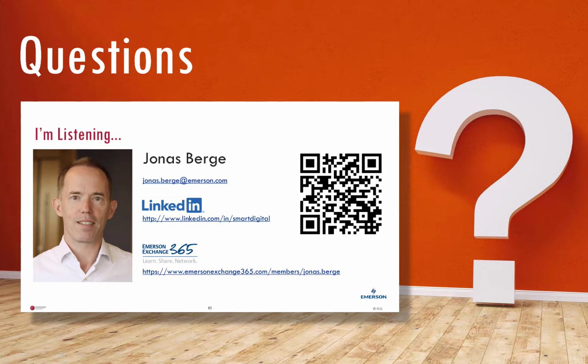Okay, here's another question. If I set the update period to 5 minutes, does measurement also take place every 5 minutes, or is measurement real time? No. If you put a 5-minute update period, that means the sensor sleeps for 5 minutes, then wakes up, makes a measurement and then transmits that measurement, okay? So it doesn't measure in between. There's a very simple reason for that. The sensor usually consumes more battery than the radio, okay? So if you make the measurement, you might as well transmit it.